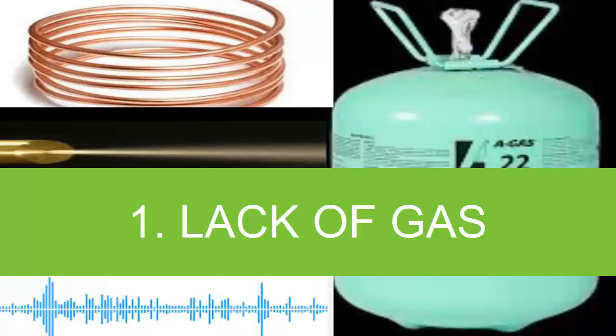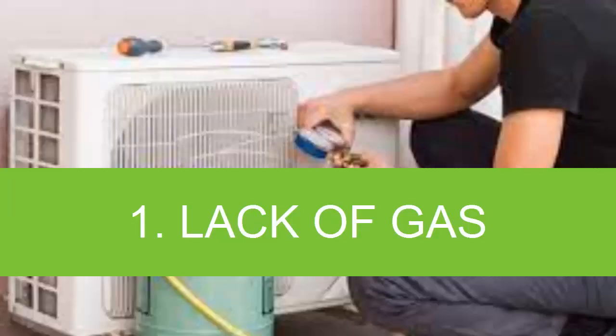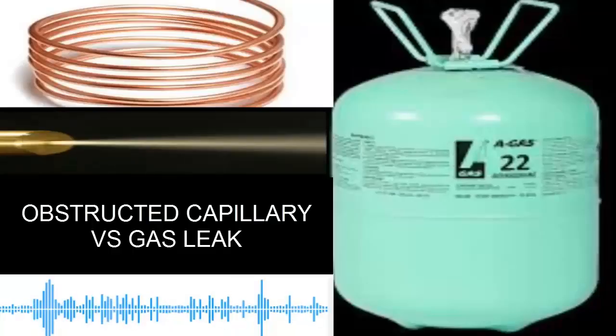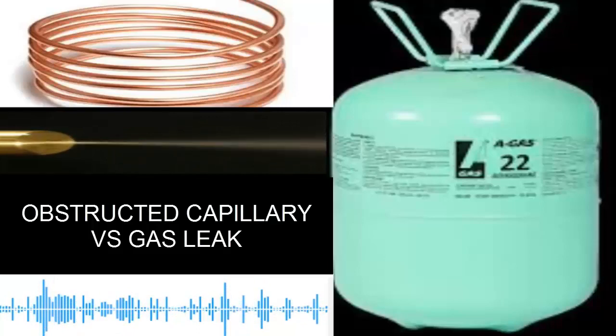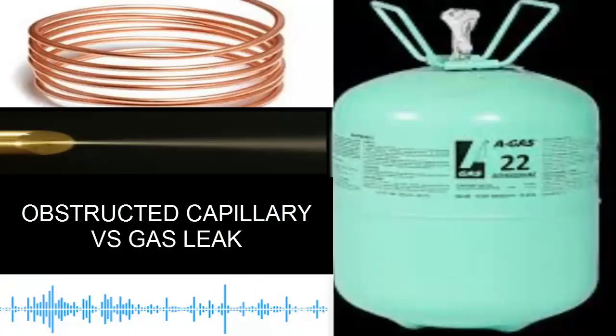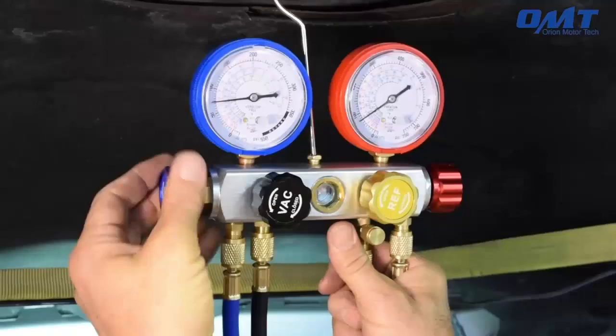1. To confirm the lack of refrigerant, the following three symptoms must be met. A. A common symptom of the lack of refrigerant in refrigeration equipment is a lower than normal refrigerant pressure on both the high and low sides. This symptom can be measured with a manometer with the equipment turned on. The pressure will be low, depending on the degree of leakage.